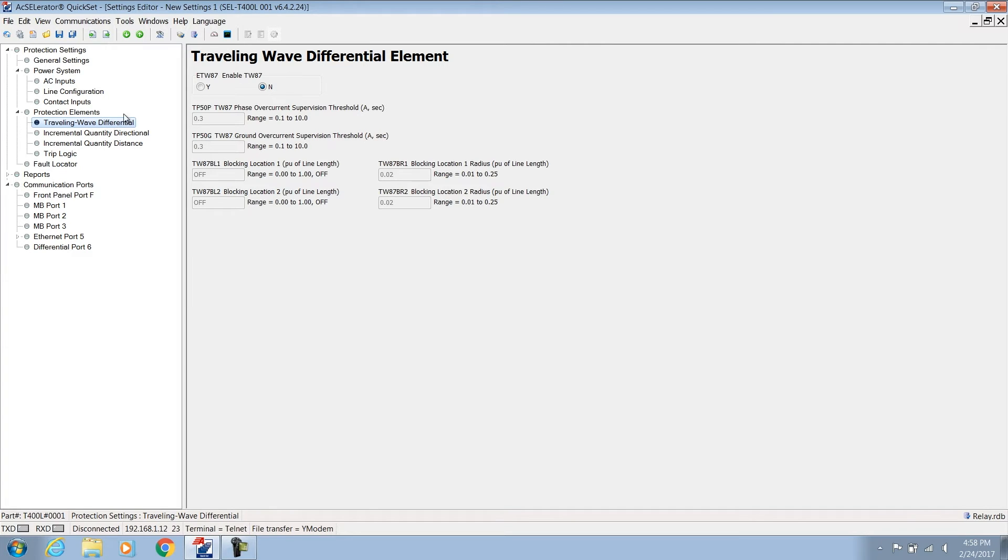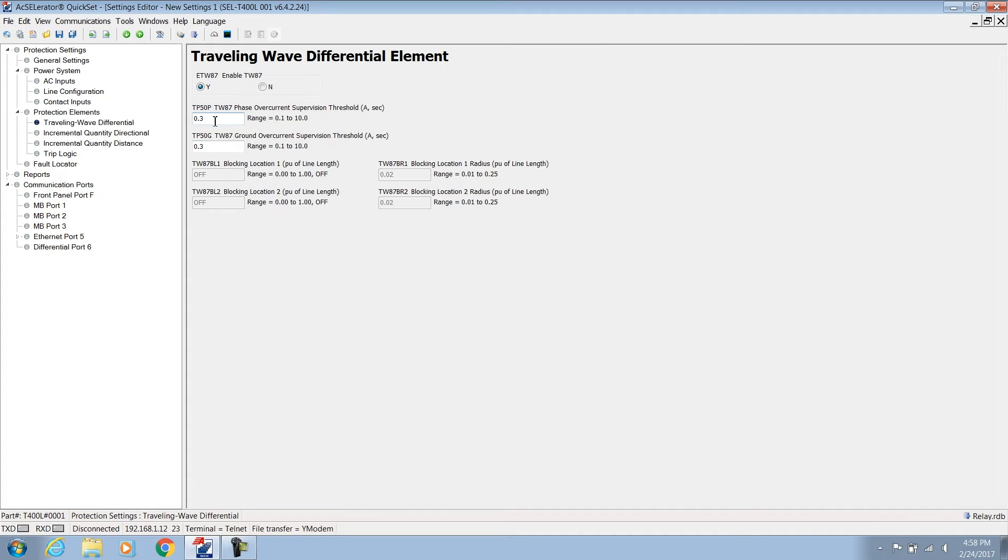To use the TW87 scheme we need to enable it and set the ground and phase overcurrent supervision levels for security. Calculate these minimum current levels using your short circuit program. Assume the weakest local system, the strongest remote system, and some fault resistance as per your utility practice. Place ground and phase faults at the remote bus and record the current values at the relay location.